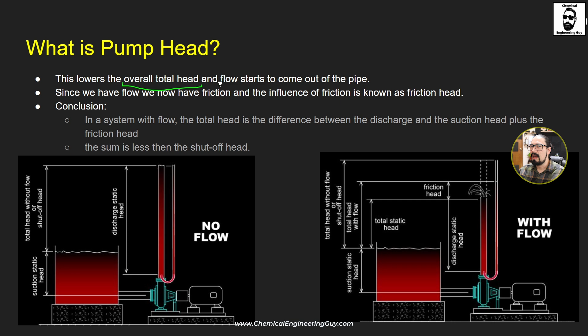Yeah, maybe to select between pumps, but in reality, this is by far one of the best criteria to select pumps. So if you understand pump head and volumetric flow rate, you're almost set up for pump selection. Now, choosing a pump with inadequate head, or let it be a lower head than required, is going to cause you a lot of pain because you're not going to be able to sustain operation. You're going to have a lot of friction losses, you're going to be operating most likely at the lowest efficiency point, and you will not deliver the required flow rate.